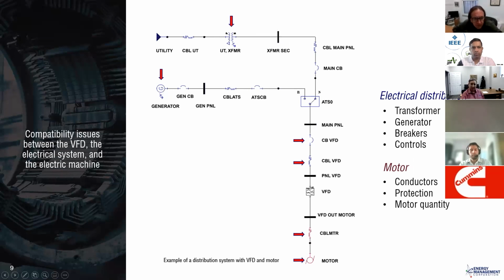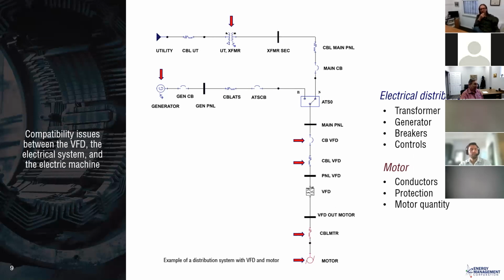Certainly the generator, we have a lot of experience with generator compatibility issues. We didn't list the automatic transfer switch here, but any kind of control could have challenges. As a matter of fact, I remember one project, probably 20 years ago, in a power plant where I think VFDs were installed on their cranes. And whenever they ran them, some of their water, I guess these might have been feed water pumps to their cooling towers, but the valves were chattering. And it came to be found that because the output of that drive in a crane was on a festoon, it was radiating noise. And every time that would happen, their valve and control system would go crazy. So certainly we're not going to talk a lot about controls today. This is more the power side of things, but those issues do exist.